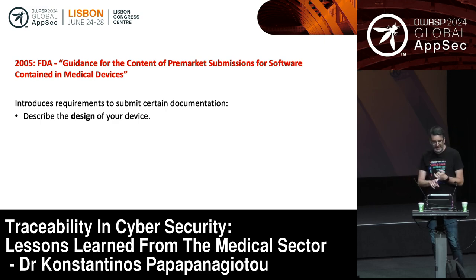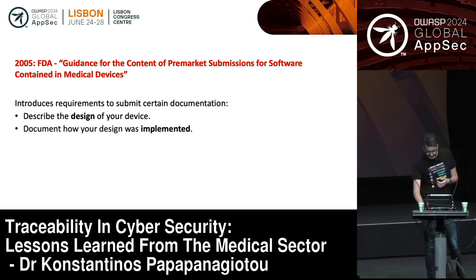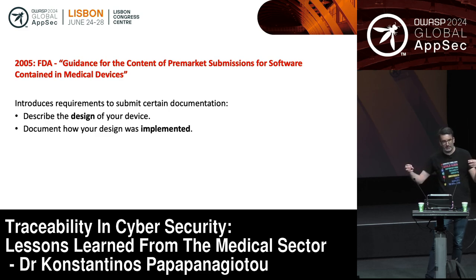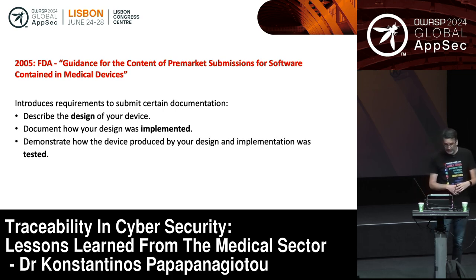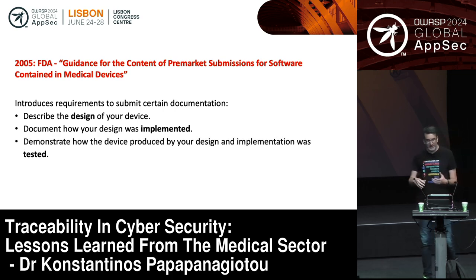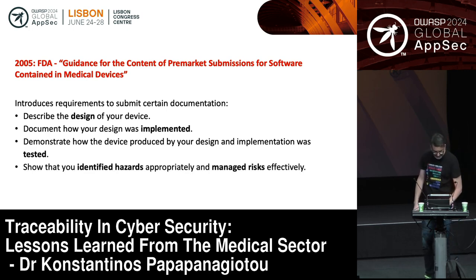First of all, FDA requires you to describe the design of your device, and requires you to document how the design was implemented. So there's a link between the design and implementation. It makes you think and prove that you implemented the way you designed the device. You need to demonstrate how the device was tested and how testing verified that the design was implemented correctly.